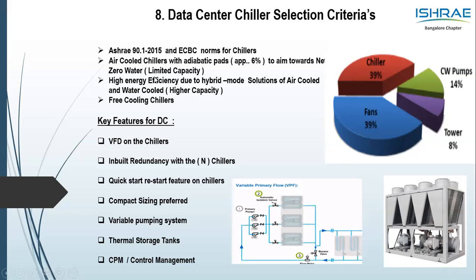Air cooled chiller, yes. As I spoke in the pledge for sustainability, keep a check on the water. The limitation on an air cooled chiller is that it is up to a limited capacity. You could have an adiabatic pad if there is water available there. You could save close to 5-6%. And also look at a hybrid module between air cooled and water cooled, thereby you save operational cost. A couple of options of free cooling we do have in the chillers. That's also very important while we design the chiller.